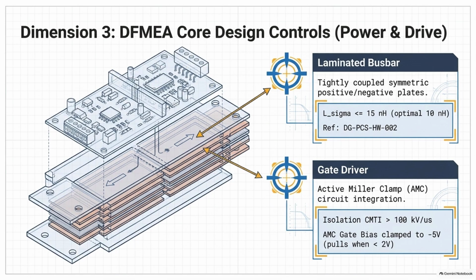The specs mention a strict design rule here. DGPCS HW-002. It's regarding the high-voltage bus bar. It demands a highly compressed, symmetrical sandwich structure. I understand that placing the positive and negative copper plates incredibly close together with an insulator in between causes their opposing magnetic fields to cancel each other out. Yes. But the spec strictly mandates the resulting inductance must be under 15 nanohenries. Ideally 10. Why 15? Why not 50? Or 5? What is the physics behind that specific threshold?